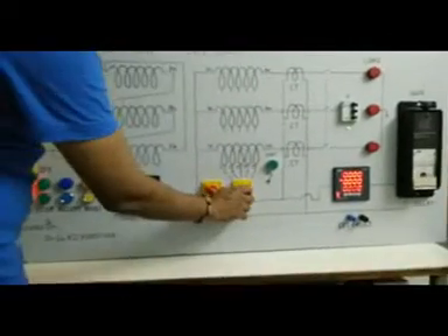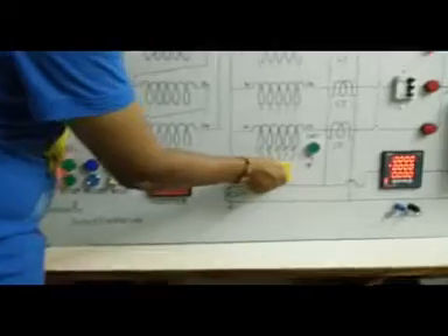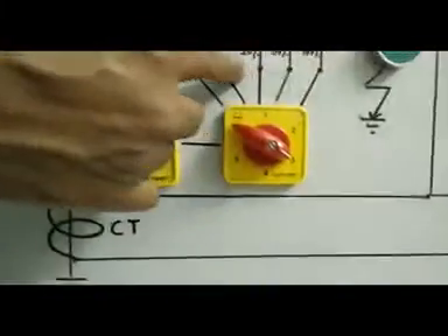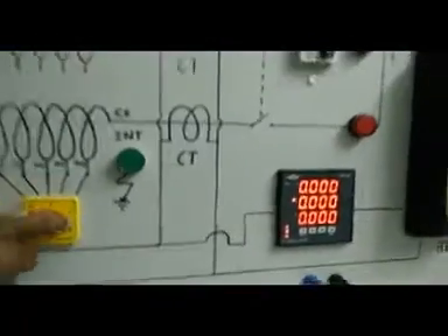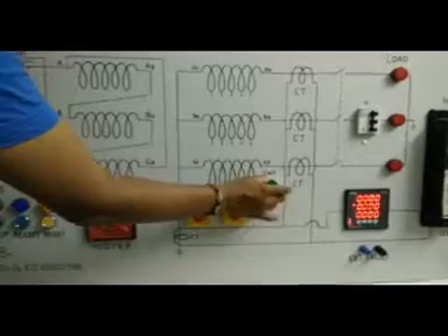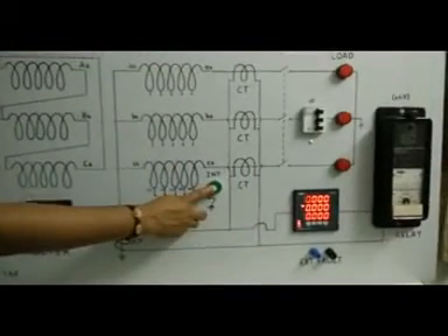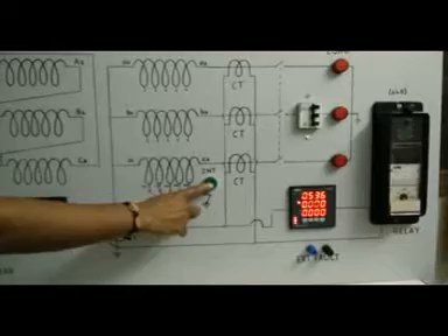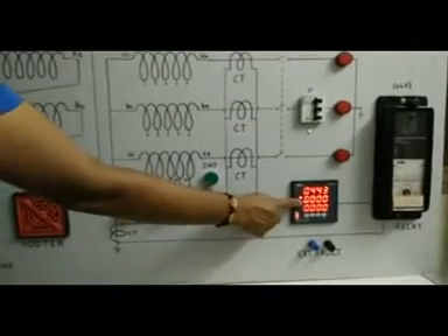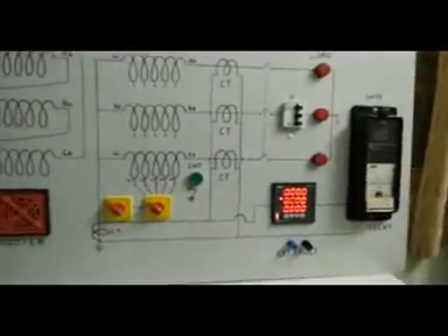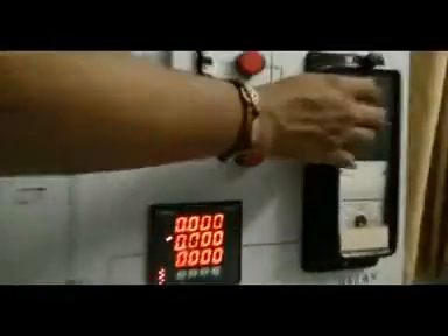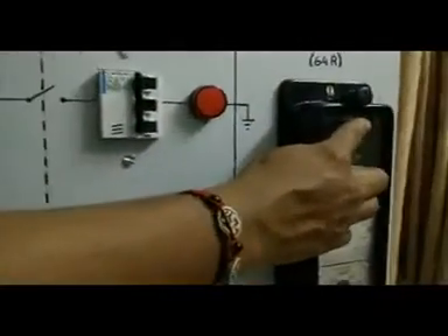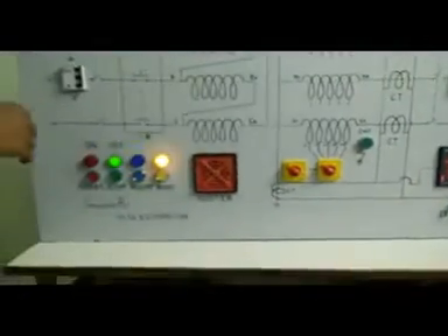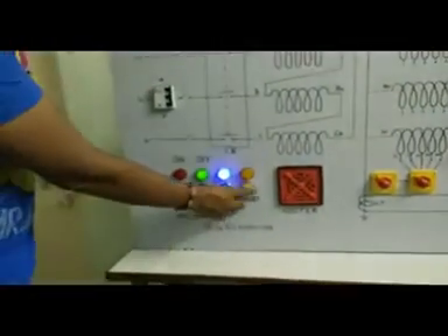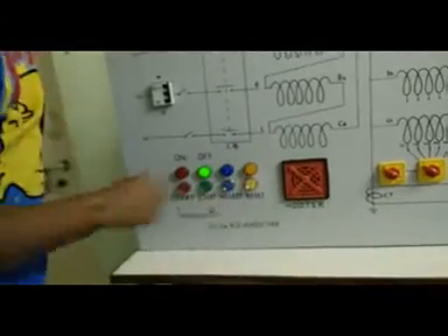So now we'll generate the fault at 20%. Even if you select 20% of the winding, you will be able to see the fault current at 20%. So let's create the fault. Please do have a look at the fault current. So the fault current is 6.8 amperes, and the protection is, the flag is set. You can see the flag, and the protection is operated in the mode. So let's hit the fault and reset the whole system.